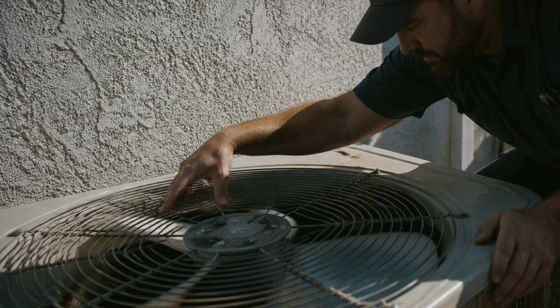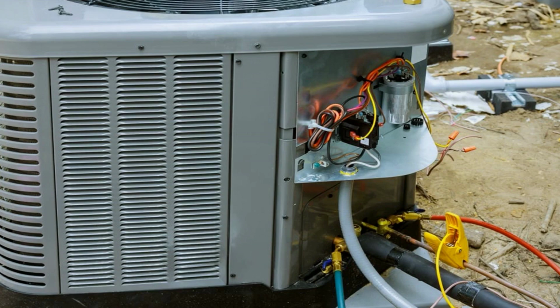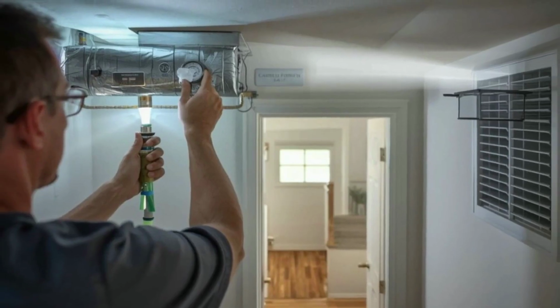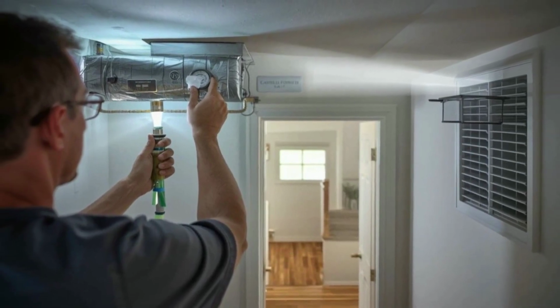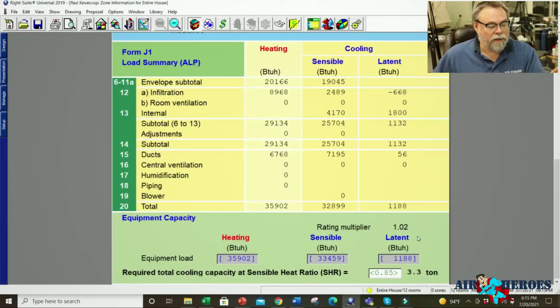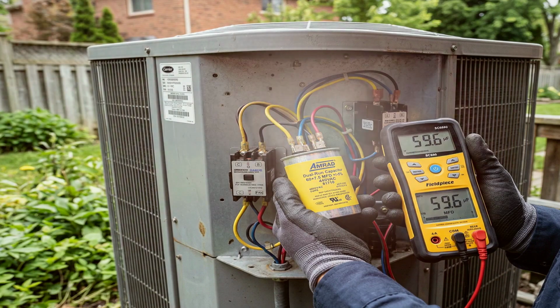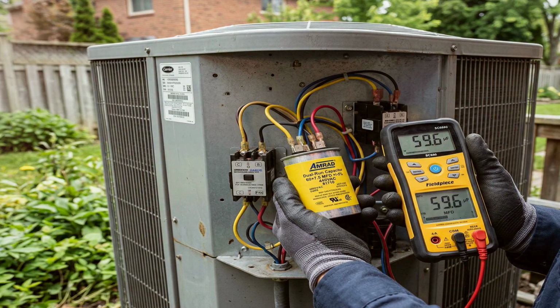A second classic symptom is a fan blade that spins only when given a manual push. The motor has just enough power to maintain rotation, but not enough to initiate it. Systems may also start briefly and shut off within seconds, or run continuously while delivering only warm air through the vents. The multimeter test gives you a definitive answer before you spend $1.